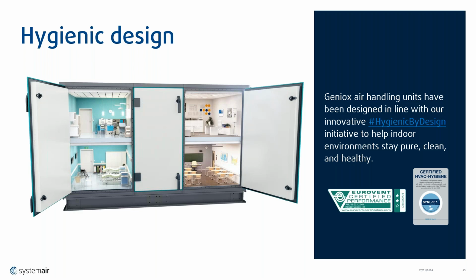What that means is that all the sealants and the plastics within the unit will not have any bacterial growth properties on them. So it's a VDI certified sealant as well as the plastics. The unit can be cleaned, which means that all components can be slid in and out on rails. So from a service perspective or from a replacement perspective, all components can be cleaned. And then lastly, you're not allowed to have any sharp points or any cuts within the unit, which can make the unit impossible to clean and maintain. So those are the general certification rules which we have from a VDI or from a hygienic perspective. And those are standard within our units, right off the shelf.